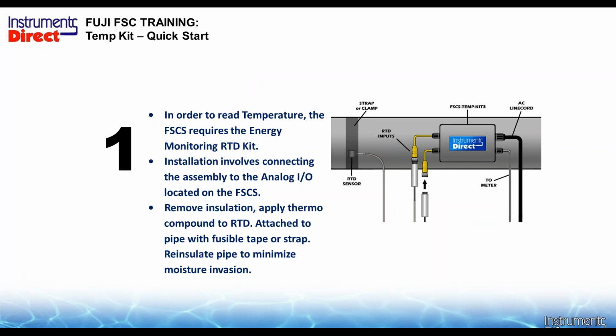It's the FSCS Temp Kit option, and basically this involves connecting the strap-on RTDs, not wetted. It's strapped on the outside of the pipe, which may be a degree or two different from the internal temperature of the process liquid. The key to BTU monitoring is accurate differential temperature. The actual temperature is secondary. So if you install it properly there, you can have an excellent BTU calculation done with a strap-on sensor. And so the way we do this, of course, we use a precision, very accurate RTD. We are not using an inexpensive temperature sensor. These things have incredible accuracies there, and when they come from us, they're calibrated as a matched pair. So it's plug and play. There's no calibration for you to do. You slap it on the pipe, and they're ready to go, basically.